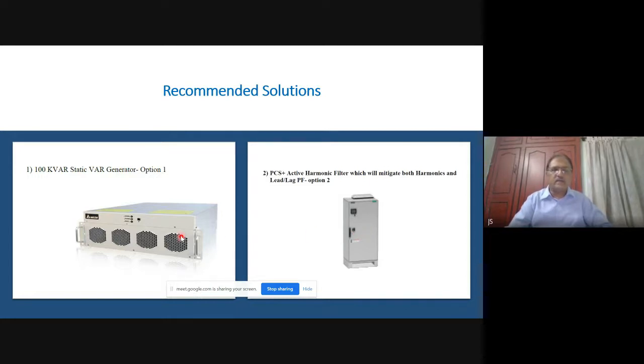So here, since the client has a rented building, the owner of the building will spend the money, a small amount of money, on providing a static var generator and ensuring that the leading power factor does not cause any penalty in the power bill. But if the building is owned and the long-term benefit of controlling the harmonic as well as the power factor has to be addressed, then the active harmonic filter is the best choice available. These are the 2 recommended solutions.